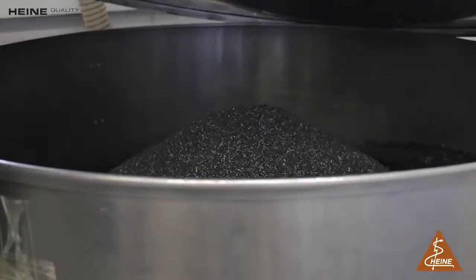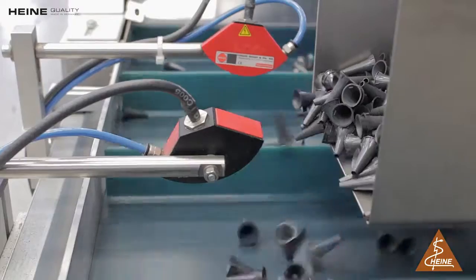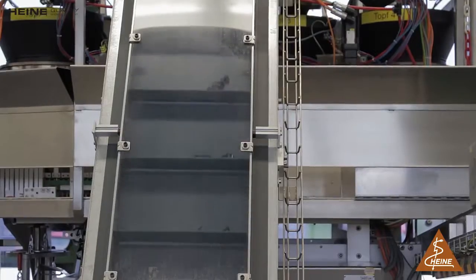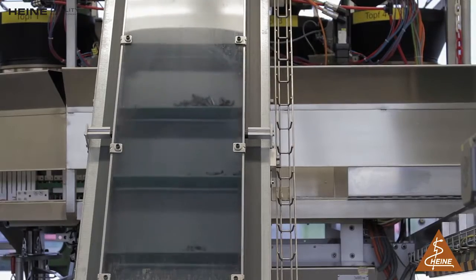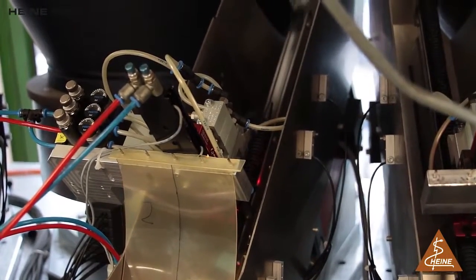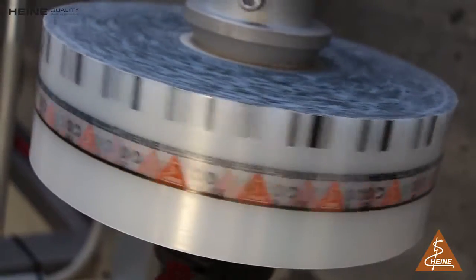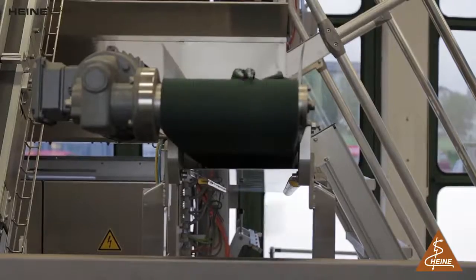The raw material for our tips is a special granulate. Once the material is at the factory, there is absolutely no direct contact with the material. The granulate is then dried out for 2–3 hours to ensure that there is no moisture held within. The heated material is then injected into the mold, solidifying and strengthening under 1,000 bars — a level where 35 tons is needed to keep the mold together — while still coming out with a perfection and accuracy of 1 hundredth of a millimeter.